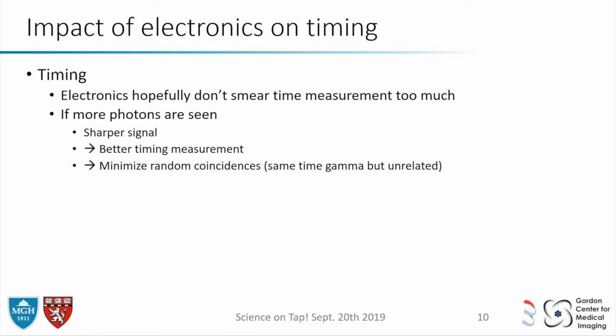What's the impact of electronics on timing? As with the crystal, decay time and number of photons impact performance. If the electronics are noisy, you won't have good timing. Electronics with stronger gain produce a sharper signal for a better trigger. You also have random coincidences — events that just happen to occur at the same time by chance. With bad timing, you need a wide coincidence window to gather all true events, but you also gather background noise. That's why you want really good electronics.